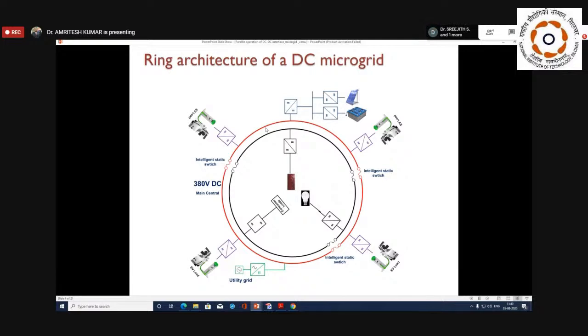One important question here is: what should be the voltage level at the DC grid? It depends. As per the standard, generally 380 volt and 48 volt are two different standards for the low voltage side. Basically, I'm talking about the distribution side.